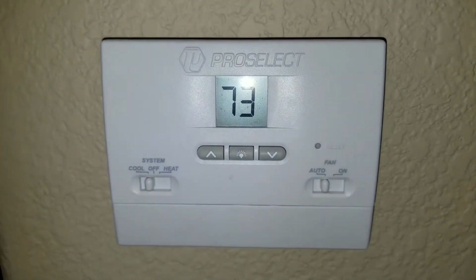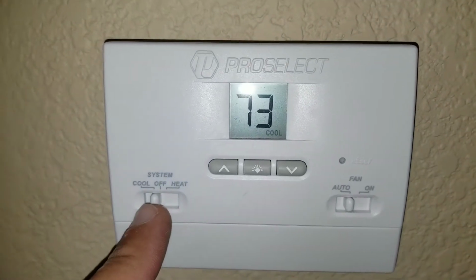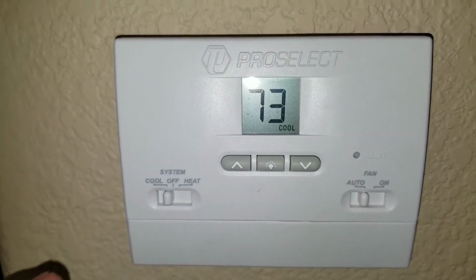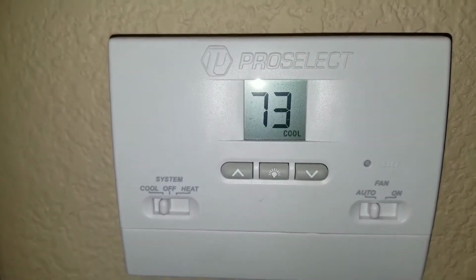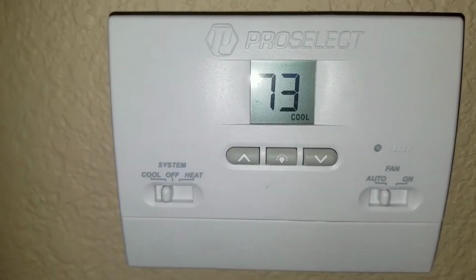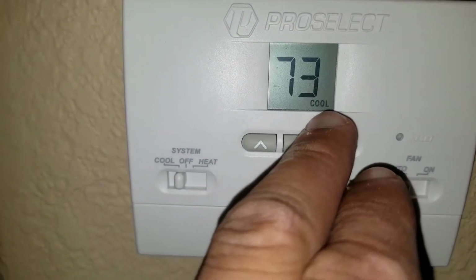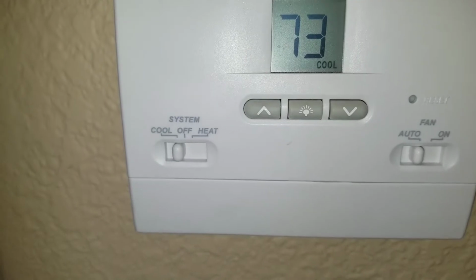So here I'm at the thermostat. It's already set to cool in auto. It was already set to this position when I came to look at the thermostat. You can see here the cool is blinking. Now at this point, I know that I have a low voltage issue.